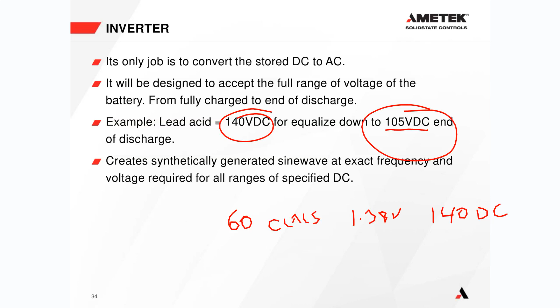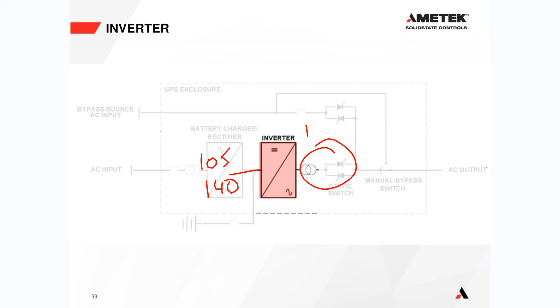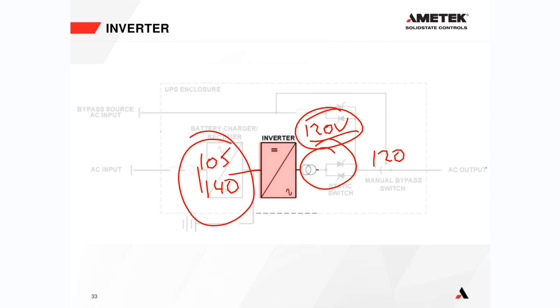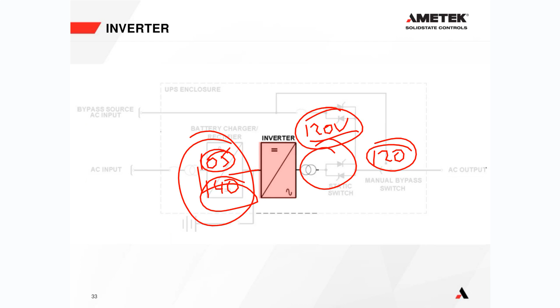So on this one here, what we're saying is we can have 105 volts up to 140 volts going into this inverter, and the output of this system is going to be 120 volts if it's a single phase system for all of those parameters. Anywhere in between, this does not move. It stays at 120 volts if it's 105 volts, or it stays at 120 volts if it's 140 volts into the inverter. That is the inverter's job. It doesn't care where the DC is coming from as long as it is between 105 and 140 for a 60 cell lead acid battery.